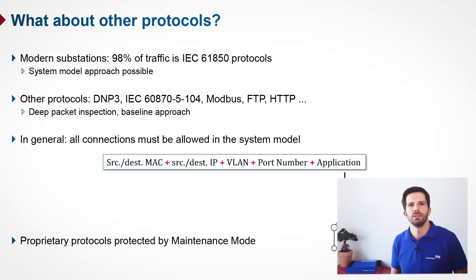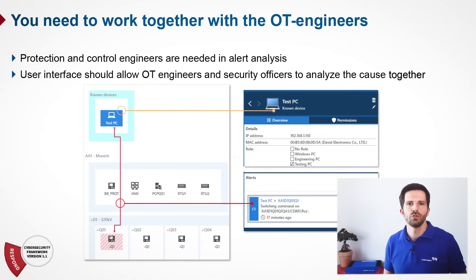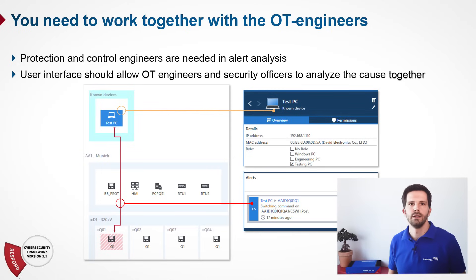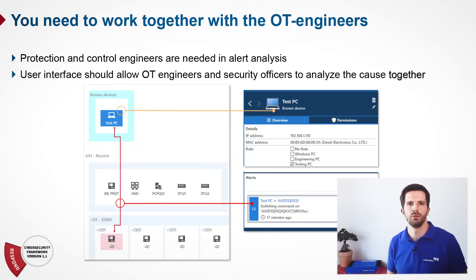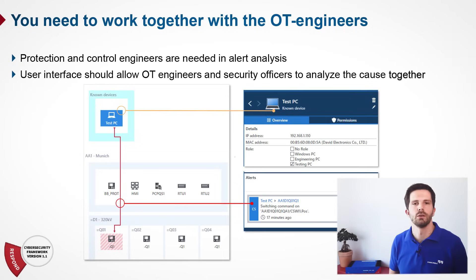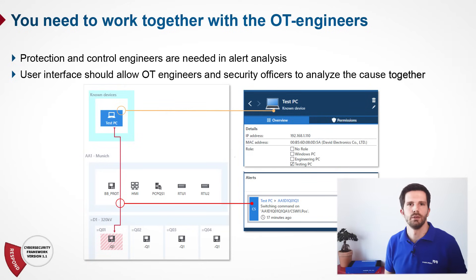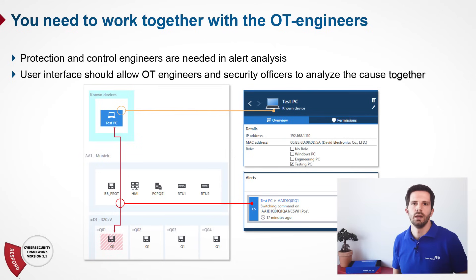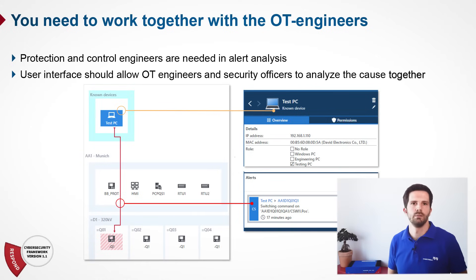An important point is that the IDS alarm display needs to be accessible for OT engineers, because protection and SCADA engineers are needed in the analysis of alert causes and in the response process. With Station Guard, the user interface is designed so that OT engineers, such as protection and control engineers, immediately feel comfortable, using a graphical diagram very close to the single-line diagram of the substation. As you can see in this screenshot, IDS alarms are depicted graphically in the system diagram — for example, as a red arrow coming from a test PC in feeder number one.